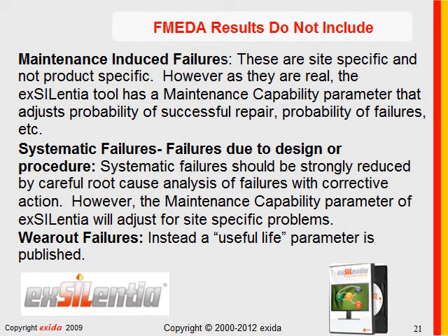It's very important to understand what is not included in the FMEDA failure rate. There are certainly two things that are not included. Well, three things. Number one, maintenance-induced failures are not included as a product attribute. They should be modeled, and in fact in the exSILentia tool, they are modeled with a separate mechanism which we call maintenance capability, which is site-specific.